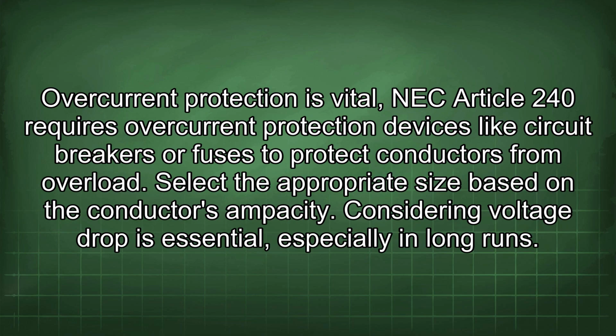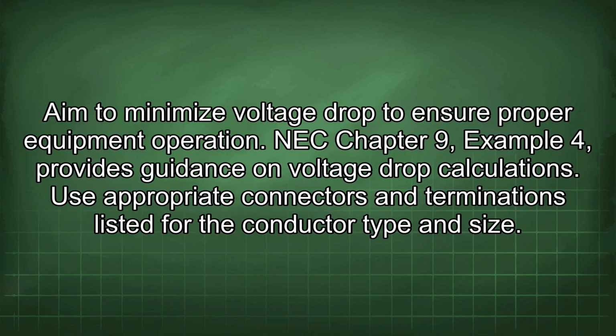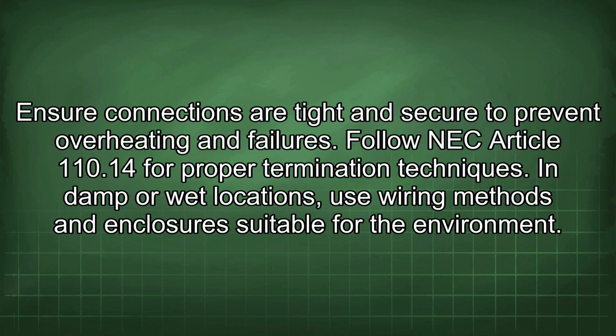Considering voltage drop is essential, especially in long runs. Aim to minimize voltage drop to ensure proper equipment operation. NEC Chapter 9, Example 4, provides guidance on voltage drop calculations. Use appropriate connectors and terminations listed for the conductor type and size. Ensure connections are tight and secure to prevent overheating and failures. Follow NEC Article 110.14 for proper termination techniques.